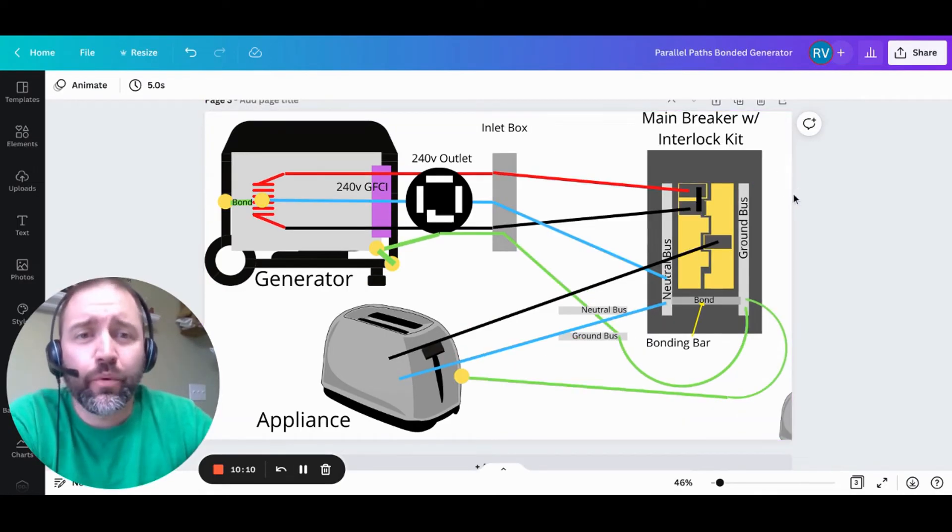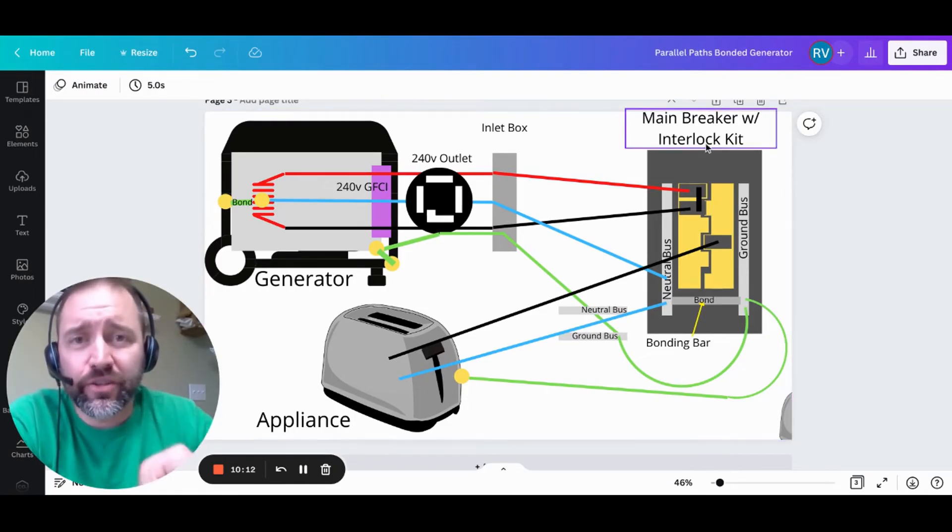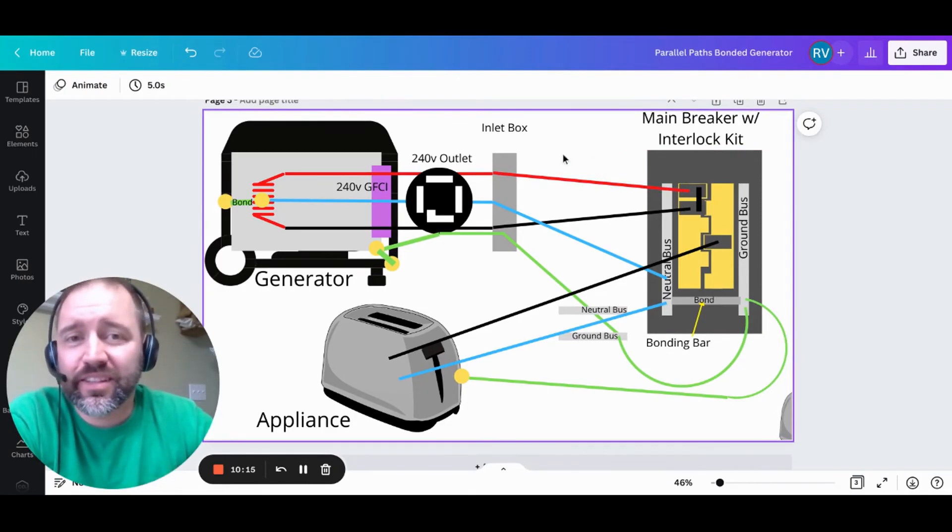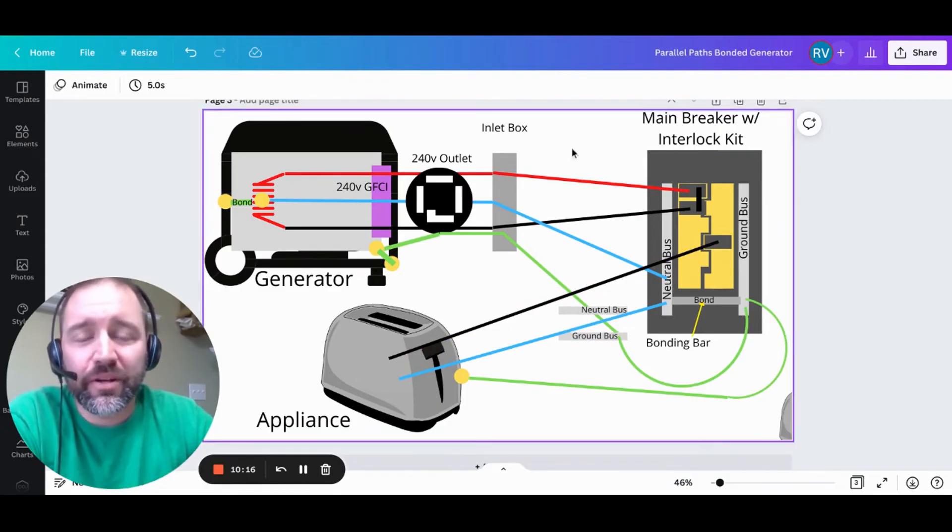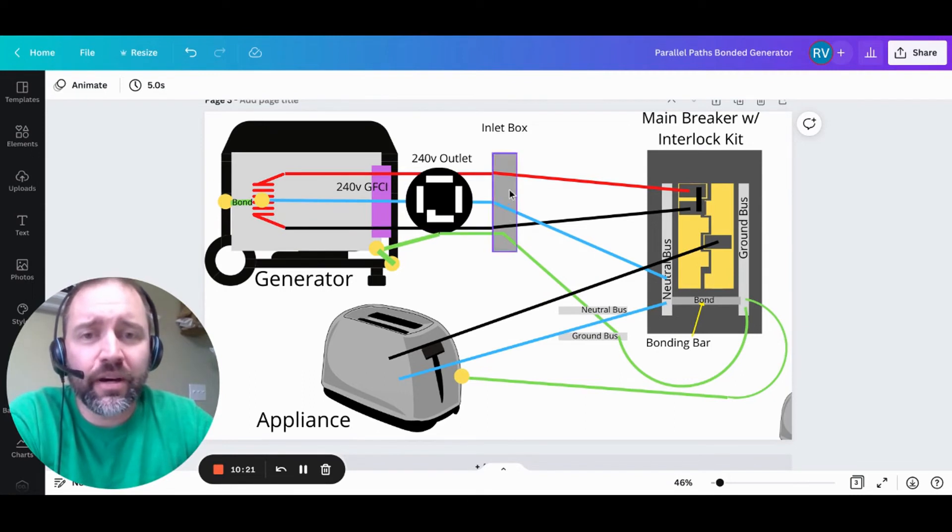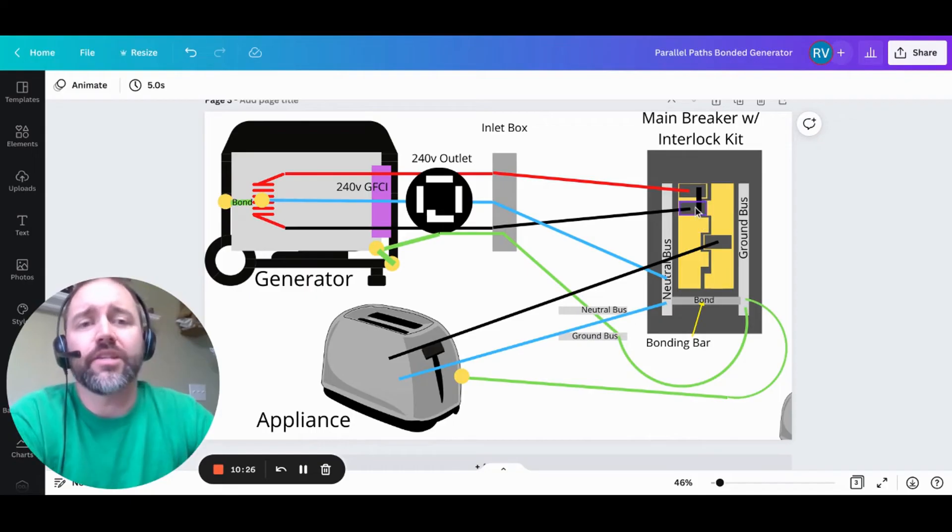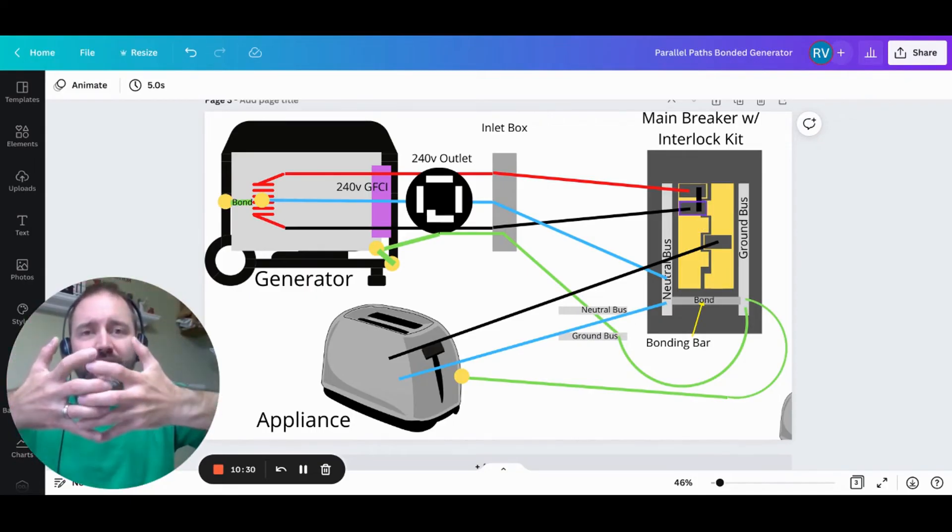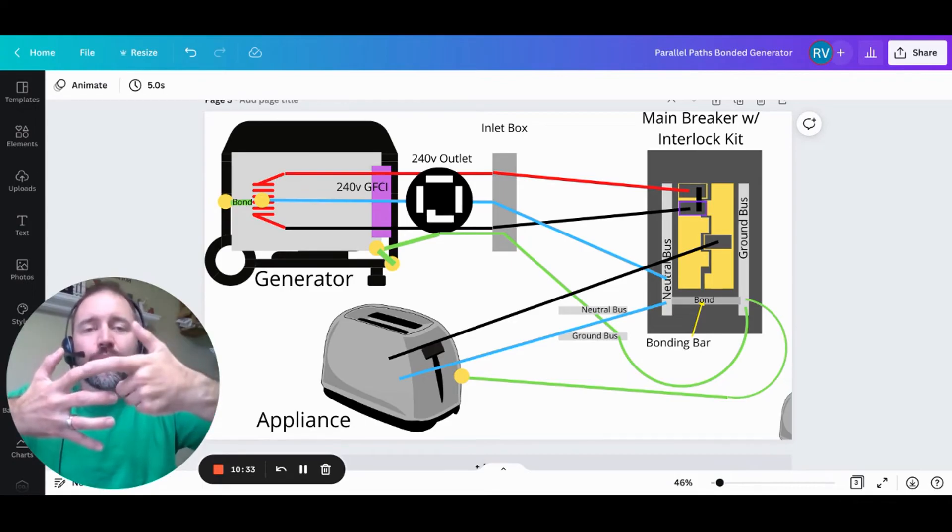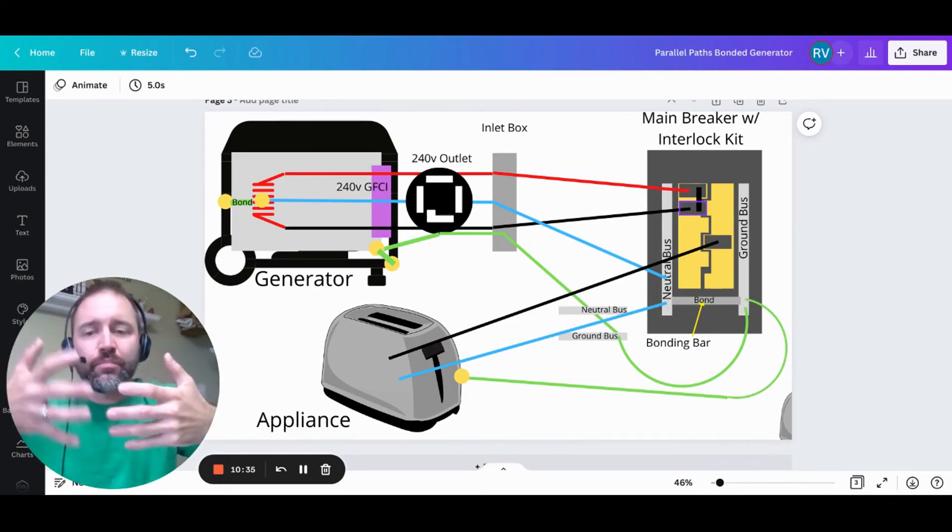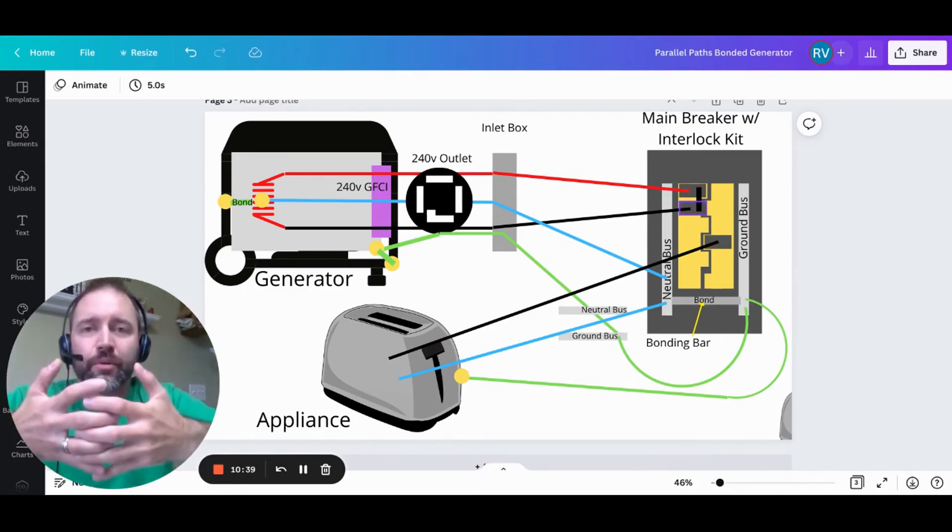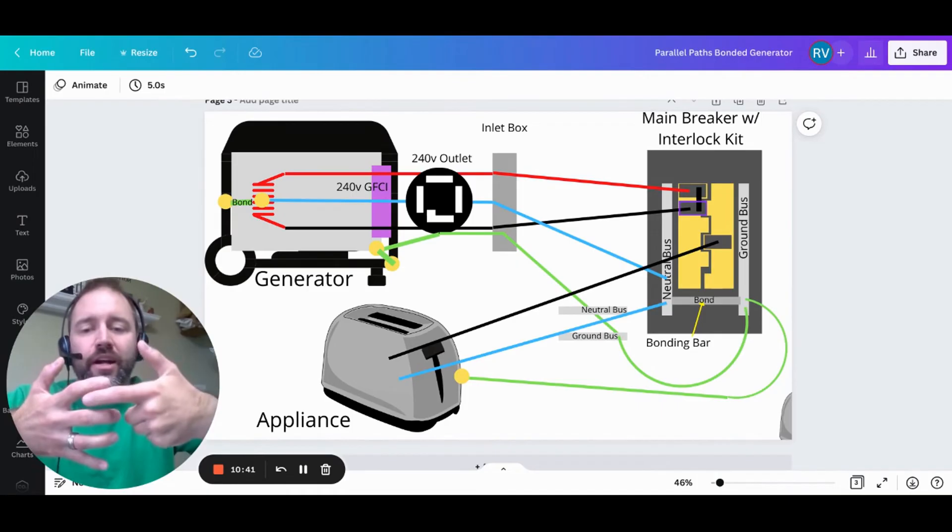Now let's take a look at what happens when we're using a main breaker with an interlock kit instead of the transfer switch. Basically, the wiring's the same. We're just cutting out the middleman here. So the electricity's still going to flow out the generator the same way as it did above, except in this case, we're going to have the two hots running to a double pole breaker. And just as a reminder, inside of your breaker box, it's going to be like interlocking fingers here that don't really touch. If you had a breaker on this finger, it would attach to this bus. If you had a breaker in between the knuckles, it would attach to this bus here. So a double pole breaker has a breaker here and a breaker in between.